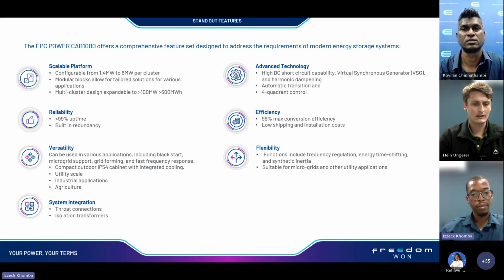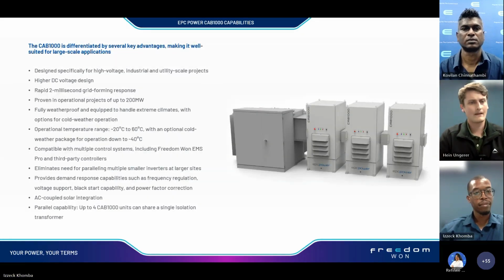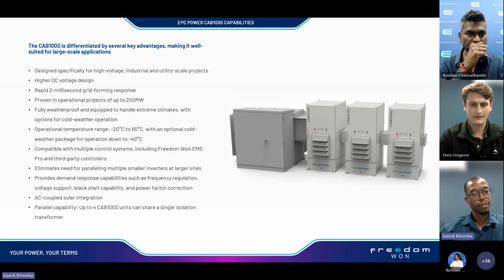Moving on to the next slide, we can go into a bit more detail. There are several key advantages, as mentioned, for utility grade applications. It has a very high DC bus voltage, quite a bit higher than our other commercial solutions. The inverter transitions from grid following to grid forming in around 2 milliseconds. That doesn't mean your site's load is transitioned within that time frame, but the inverter transitions internally to become grid forming, and then depending on the site's load and reactive power being demanded, it will take a certain amount of time for the inverter to recover the bus voltage. It also depends on the external switchgear of the site.